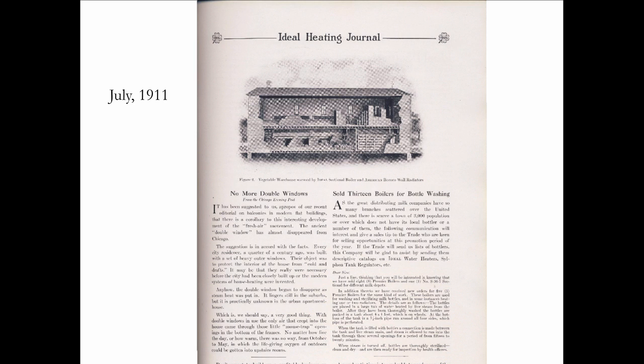This is also why you'll see radiators installed under windows. When you think about it, if you've got a room with a heat loss of, say, 10,000 BTUs, it really doesn't matter where in the room you put that radiator — it could be mounted onto the window, on an inside wall, or even on the ceiling. In fact, if you've been around enough steam heat, you'll see plenty of radiators mounted on the ceiling, many times on lower floors to get them above the boiler water line.